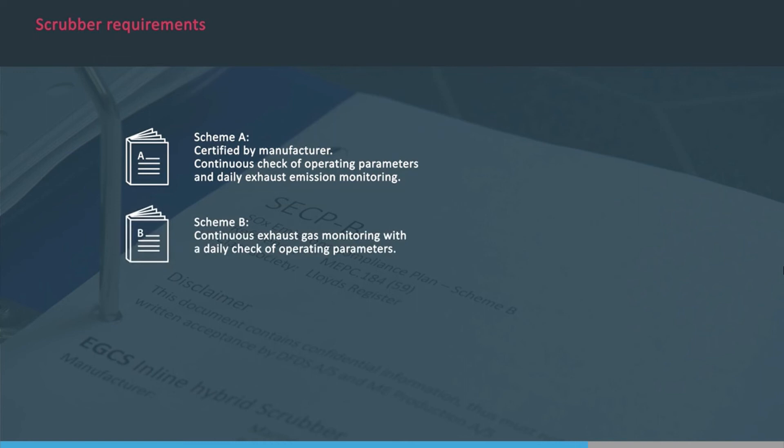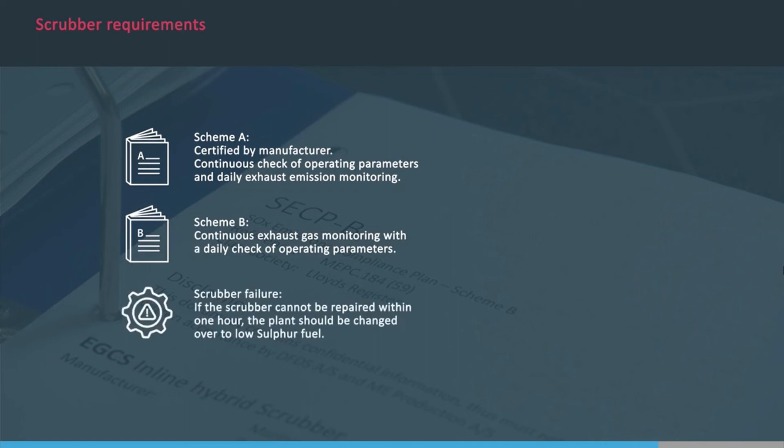Scheme B, based on continuous exhaust emission monitoring, together with a daily check of operating parameters. In general, if there is any failure of the scrubber that cannot be repaired within one hour, the plant should be changed over to a low-sulphur fuel, which ensures compliance with local regulations.